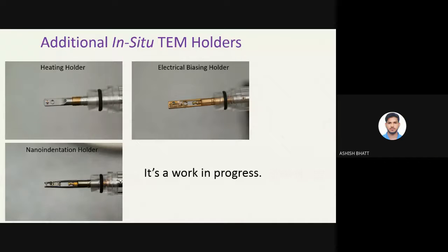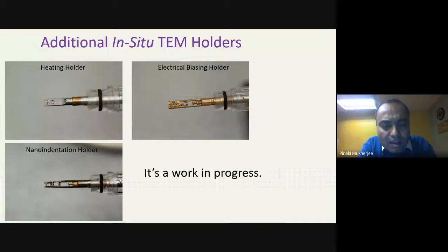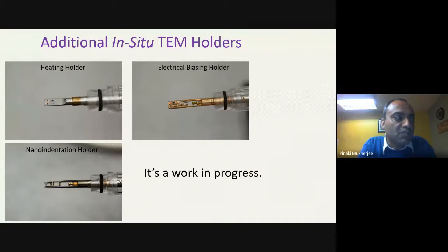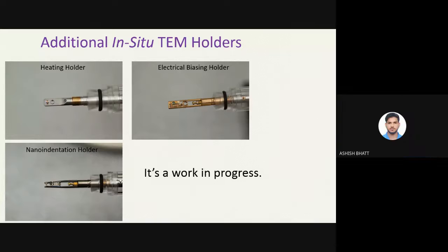Sir, in TEM, we use magnetic lenses. Sir, in a magnetic lens, how do we change the focal length? Focal length, you just change it by the objective lens current. These are electromagnetic lenses, all right. Whenever you change the knob, say the objective or focus knob in your TEM, it actually changes the current in the solenoid, and that way you can change the focal length. Okay, sir. Thank you so much, sir.